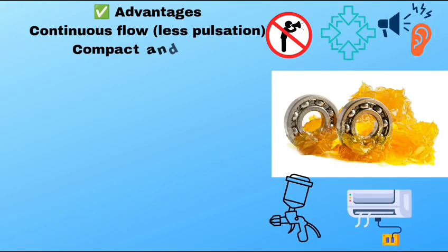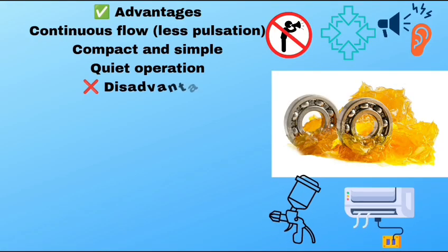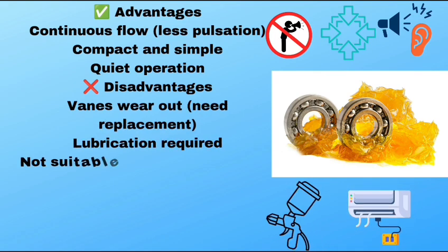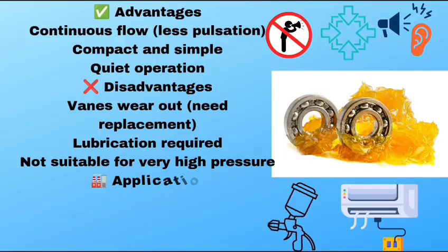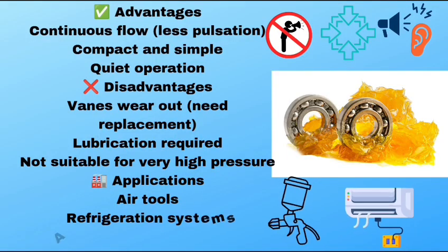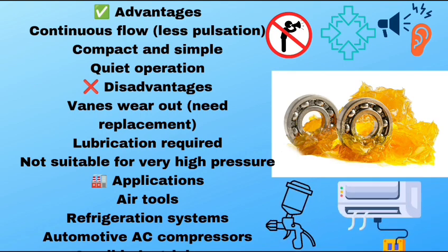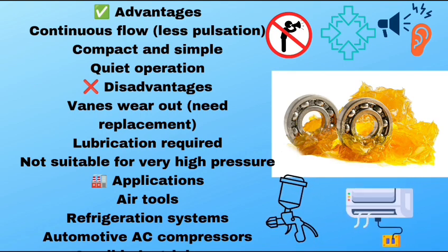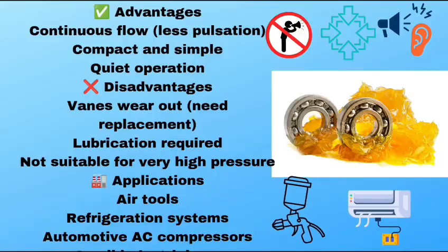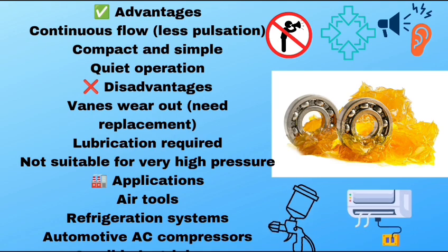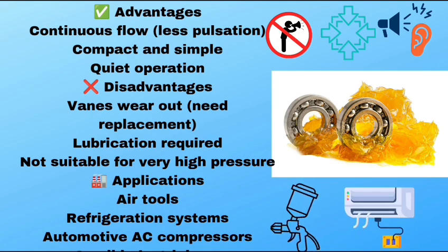Advantages of the vane compressor are continuous flow, compact and simple design, and quiet operation. Disadvantages are that vanes wear, lubrication is required, and it is not suitable for high pressure applications. It is used for air tools, automotive AC compressors, and refrigeration systems.